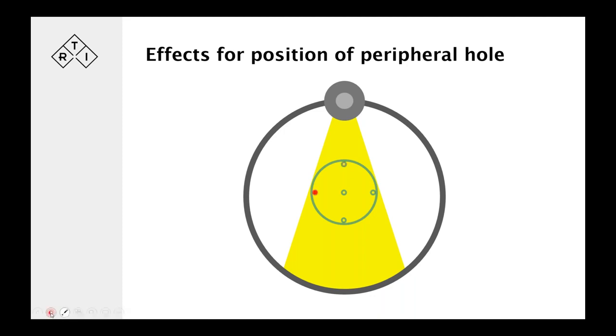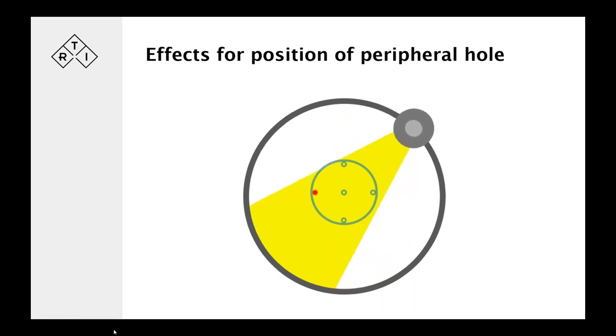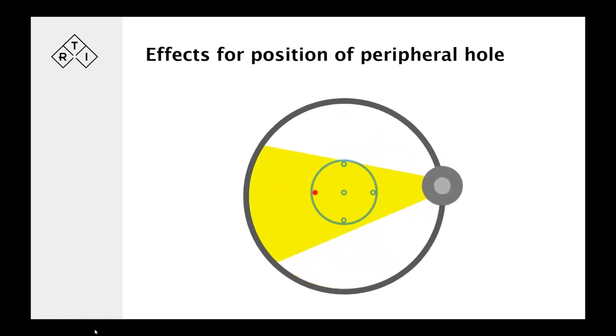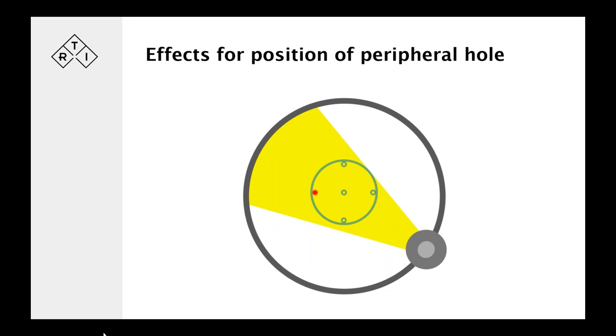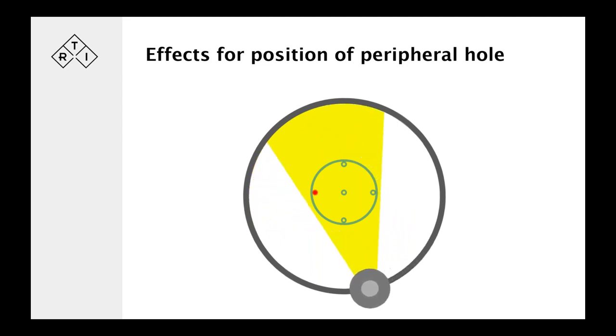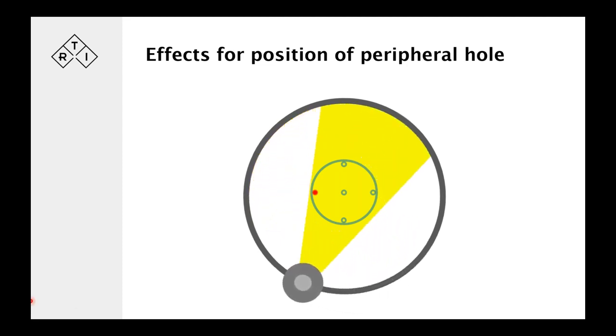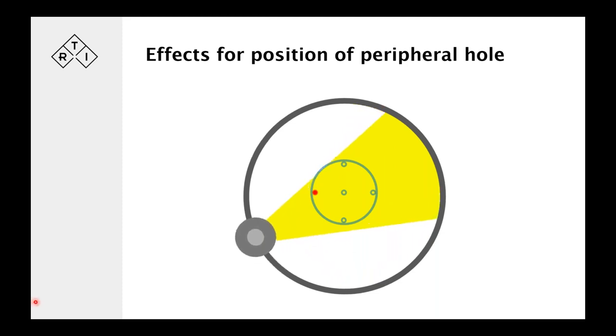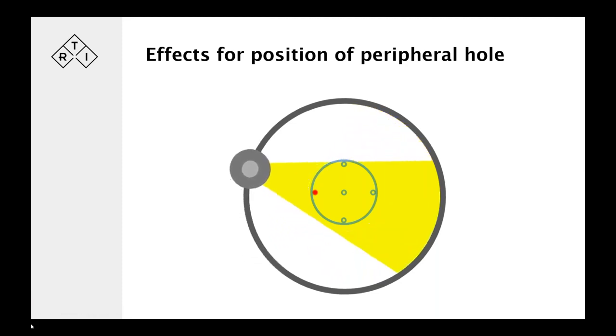And if we have an exposure that starts with the pencil ion chamber right in this position, well, of course, you'll have another pattern, where you start with not the maximum dose rate, but less than the maximum dose rate. It's only when you've rotated the tube 270 degrees that you reach the maximum dose rate for this measurement example, right in this position.